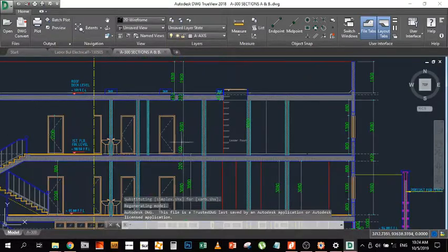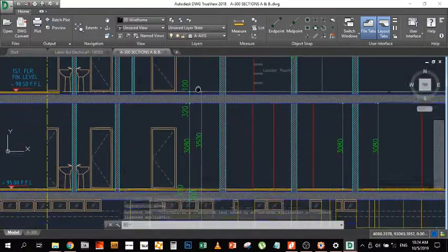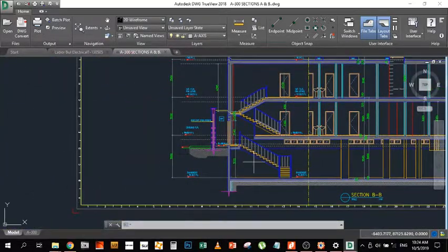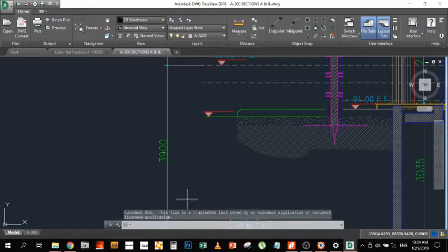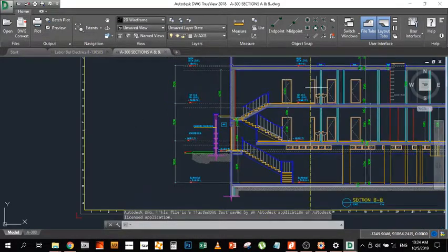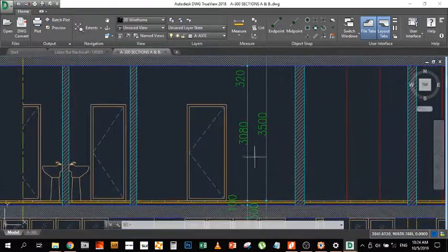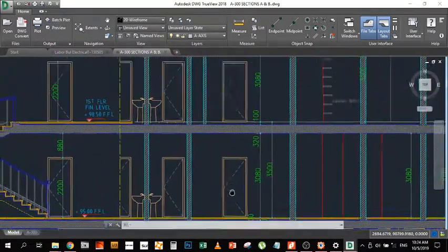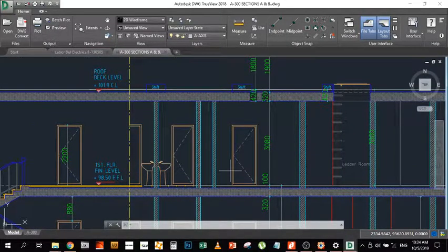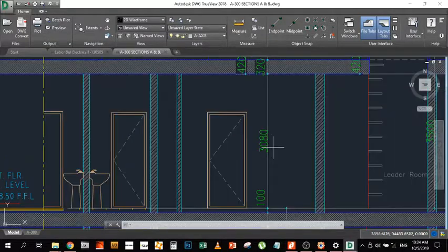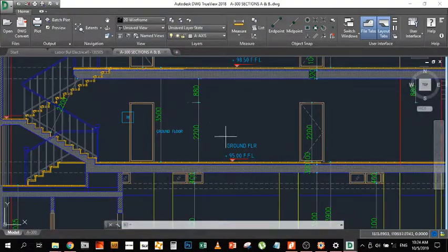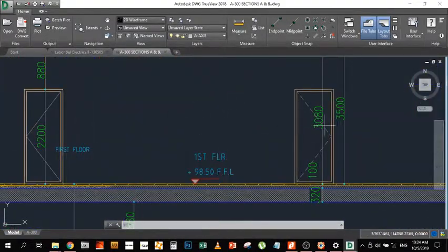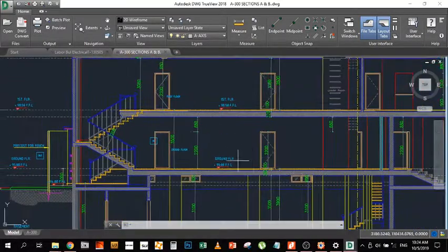So in section drawing, you will see the section across, and in this case, you can find two things. One is the complete floor height and the other is the ceiling height inside minus the floor slabs, the ceiling slabs. In this case, from what I see from the drawing, it seems that all the floors are surface mounted. So they have surface mounted luminaires and hence the ceiling height is 3.080. So for this specific drawing, our ceiling heights will be 3.080.